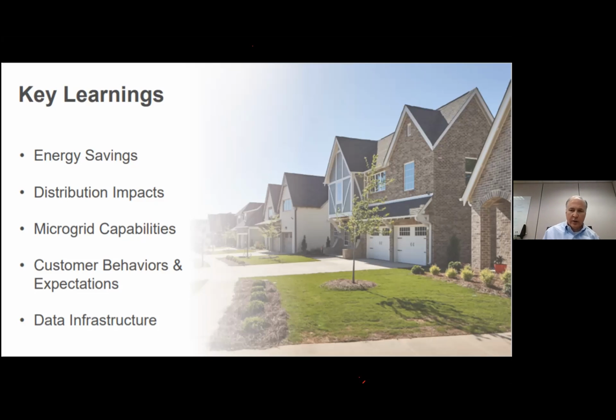Same thing with the microgrid controller: the operator would press a button to island the neighborhood, isolating it to run all the homes off the microgrid's energy. One day we were doing a test, and the operator pressed the button but wasn't sure it had islanded, so he pressed it again, which created a firestorm of failures. What we didn't know is that the manufacturer had built into the system that if you pressed it twice, it interpreted that as some kind of fault and locked everything out. We wouldn't have known that had we not done those tests. We had to work with the manufacturer to change that protocol, and give feedback to the operators so that when they pressed the button, they'd know whether the islanding had occurred or not.